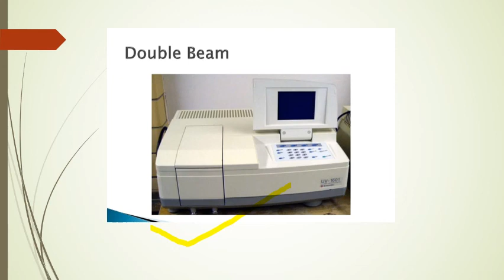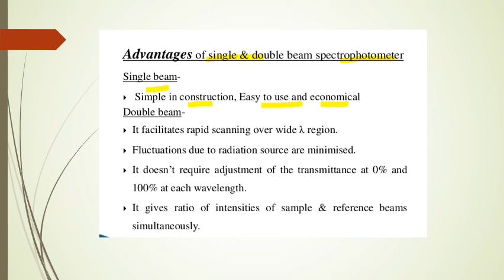So there are various advantages of the single and double beam spectrophotometers. Single beam is simple in construction, easy to use and economical. The double beam facilitates rapid scanning over a wide wavelength region. Fluctuation due to the radiation source can be minimized. It doesn't require adjustment of the transmittance at 0% and 100% at each wavelength. It gives the ratio of the intensity of the sample and the reference beam simultaneously.